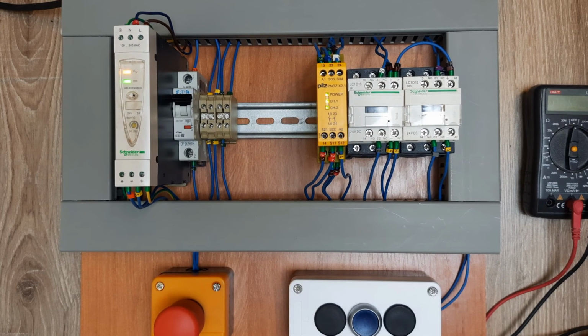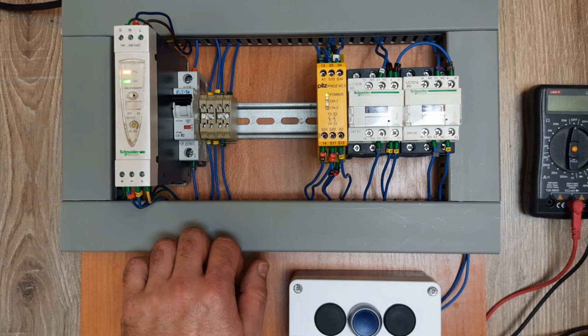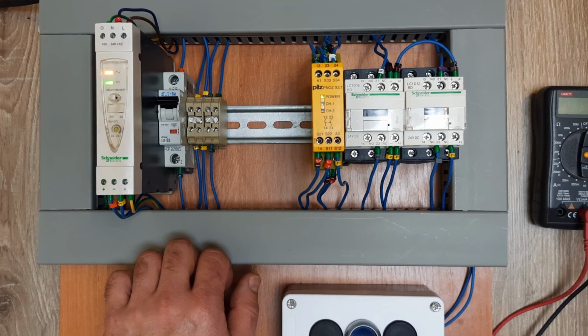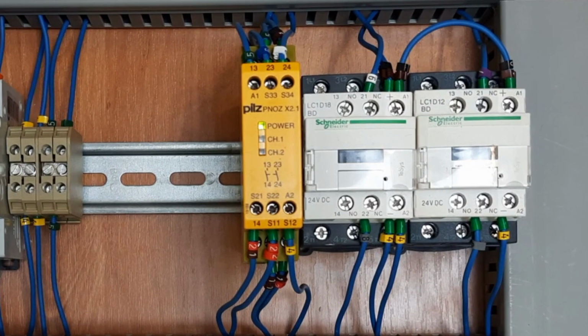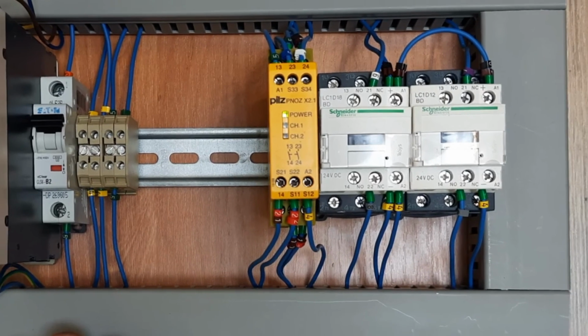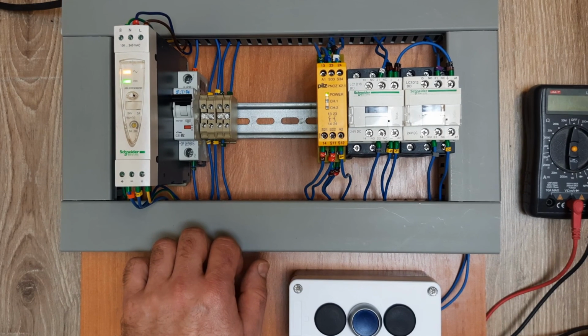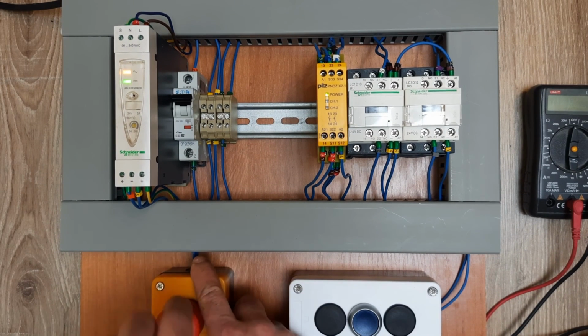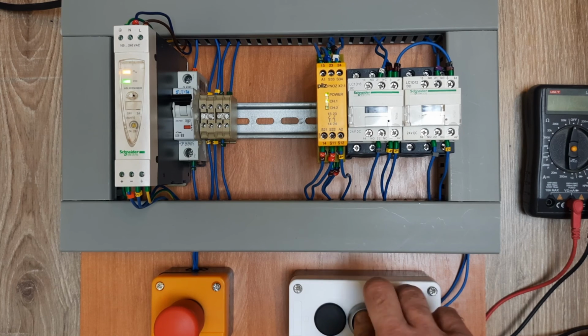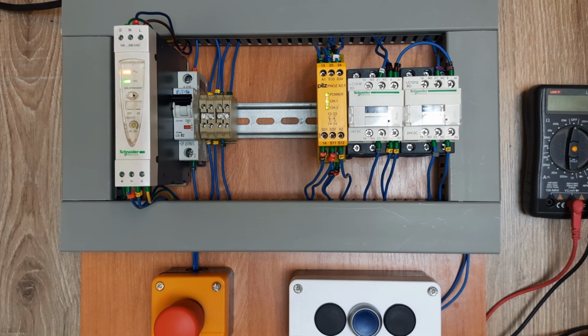What is going to happen when we press the E-stop? When the E-stop is operated, both normally closed contacts will become open, so safety inputs will become open as well. The LED for channel 1 and channel 2 will turn off, and the safety outputs will become open. To restart the safety relay, release the E-stop and press the manual start button.